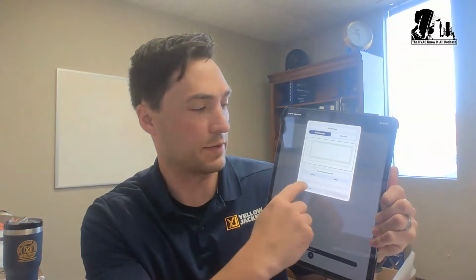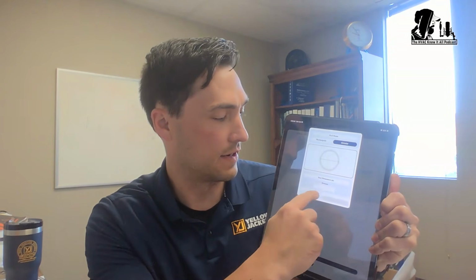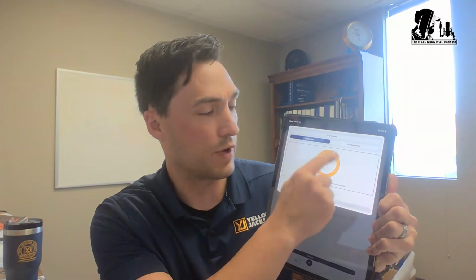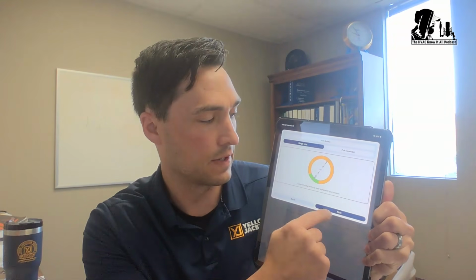Any last words, Eric, before we head out? I just wanted to show, we talked about the anemometer session a little bit quickly, but you can put in the duct dimensions, for rectangle or circular duct. Say I had a 20-inch duct - this is in inches right now, but you can change it to metric. Then you select where you're traversing the duct, and it'll tell you exactly how many points and where to measure from. You click next, and it goes through where you're measuring from, you click through each one, and then you have the whole traverse, and it gives you the full CFM.